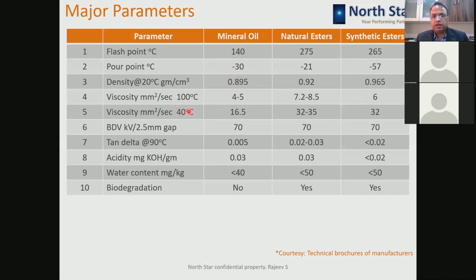At 40 degrees centigrade, mineral oil is 16.5, natural ester is 32 to 35, and synthetic ester is 32. So at 40 degrees centigrade, natural and synthetic esters are both equally viscous, and mineral oil is comparatively much less viscous compared to these two. Okay, so if you look at 100 degrees centigrade, the gap between mineral oil and these two is quite reduced. And if the operating temperature, which is possible with the esters, goes above 100 degrees, to 110 or 115, then the viscosity will come down close to mineral oil only. So at that temperature, the cooling properties of the material will be as good as mineral oil. BDV is the same for all three.